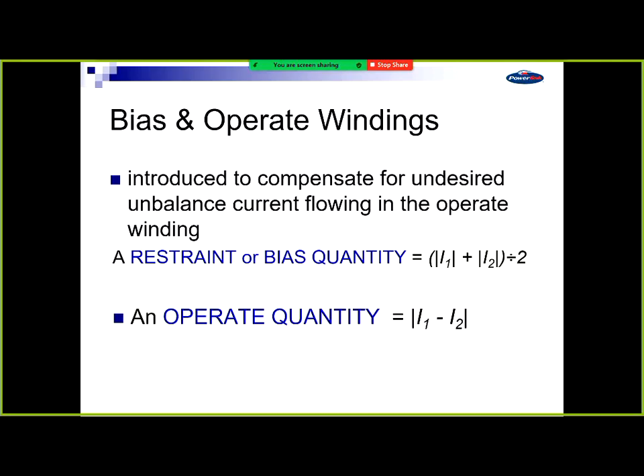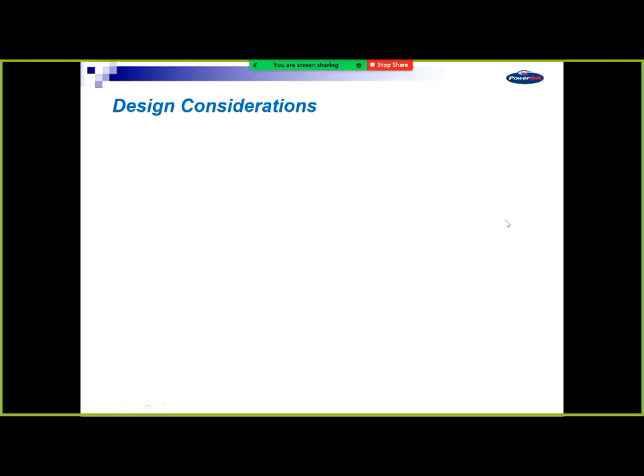That restraint quantity, the picture coming up, Siemens do it differently. So they don't have the divided by 2, I think, from memory. So you'll see that coming up in a slide, I'll point that out. It's quite simple when you're working out what you need to do and how to set these relays. You just use their equation, not this old equation. But many relays will still default to this. Others do it differently. That's why you've got to read their manual.